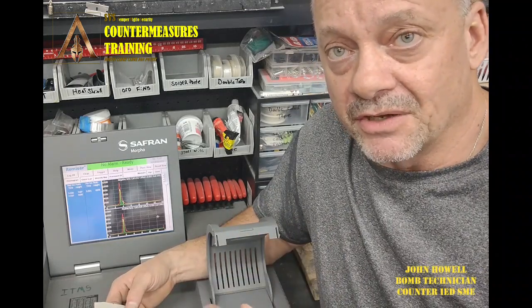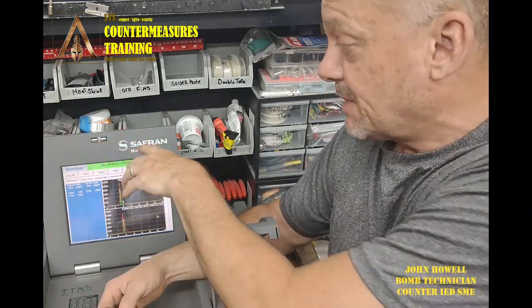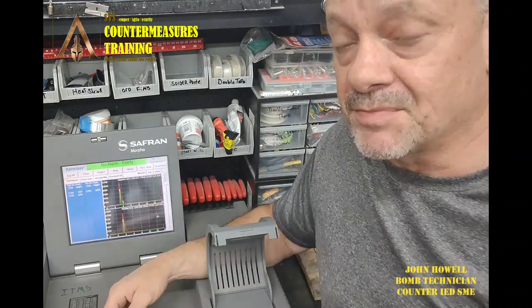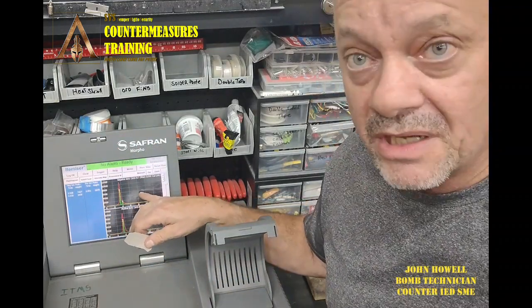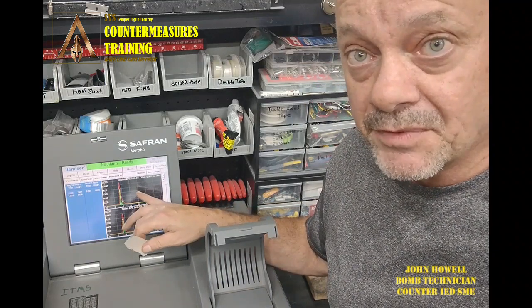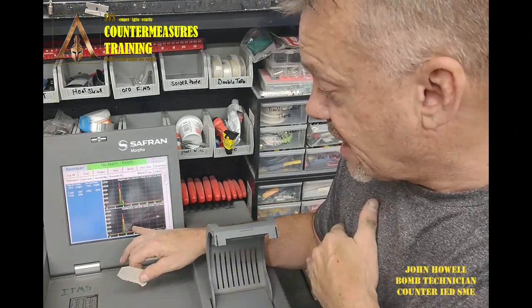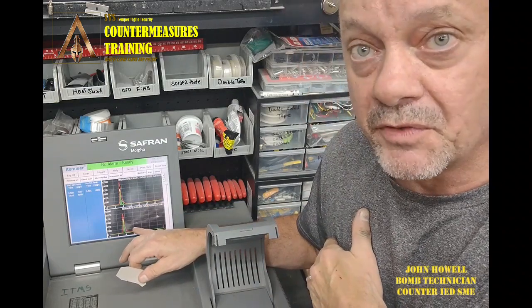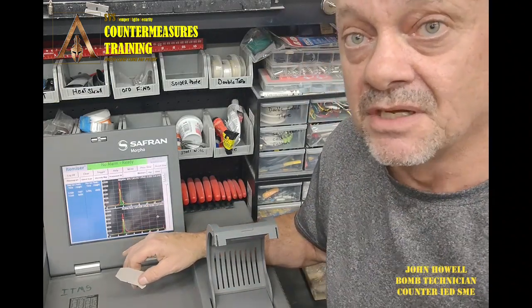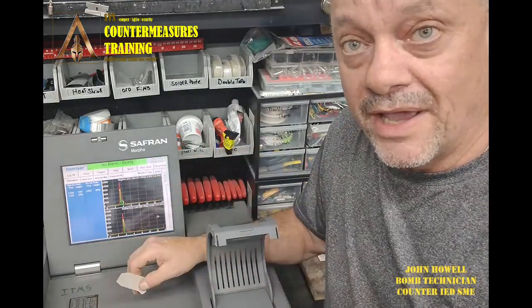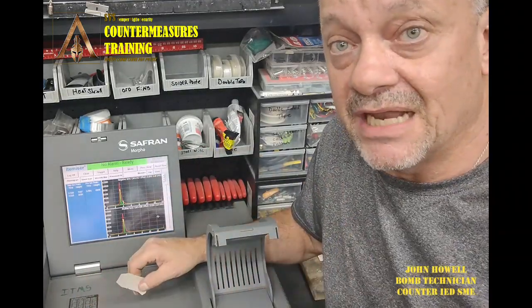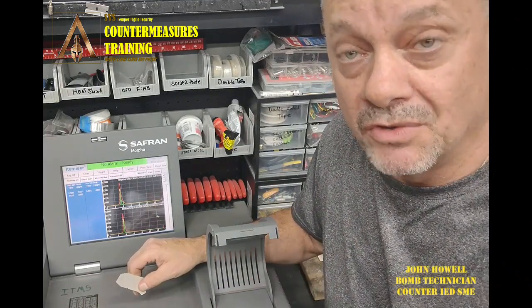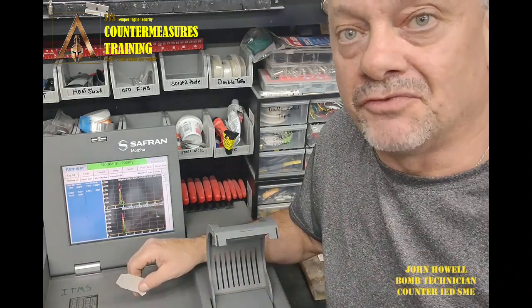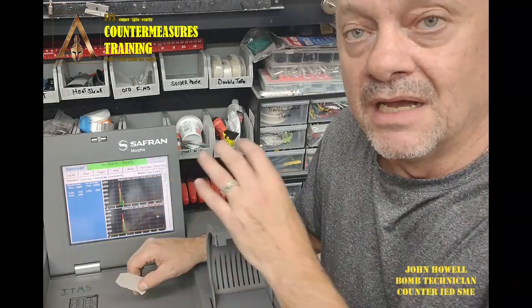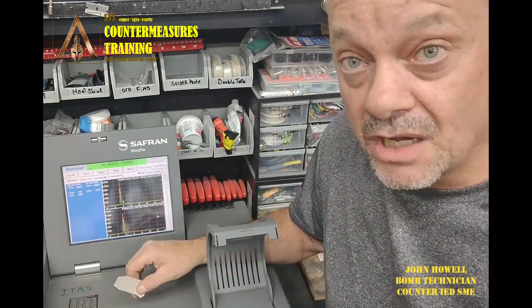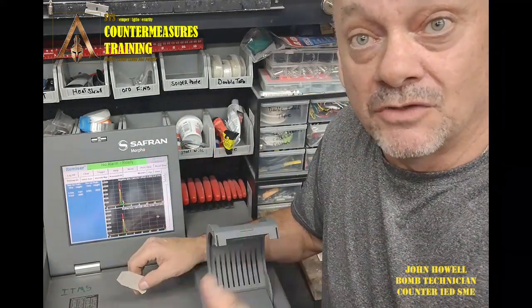There's 3 modes on here that you can run the system, and I'm not talking about what you're seeing here. This is the plasmagram. You've got the negative mode on top, which is the negative plasmagram, so negative ions, and down at the bottom you have the positive plasmagram, which is showing you positive ions. This system always scans in a positive and negative mode, so it's a dual mode detection system. Now where the confusion comes in is in the programming. When I switch it over to drugs or narcotics, those are different modes.